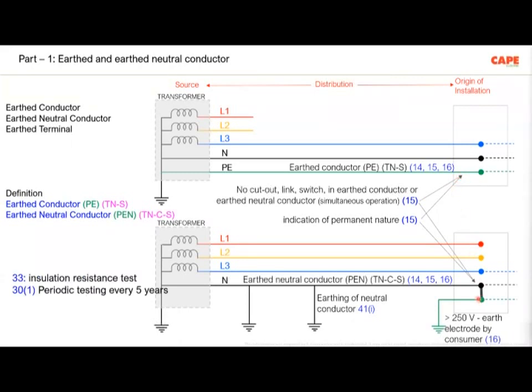And then here, where I'm moving the cursor, the electricity supply company is supposed to give an earthed terminal to the consumer, meaning this earthed terminal is connected to the neutral of the power supply company through a metallic conductor. That metallic conductor fault return path is absolutely important, because in India, the electricity distribution company gives you a cutout fuse, a porcelain fuse, and this porcelain fuse is supposed to protect our installation in case of a fault.